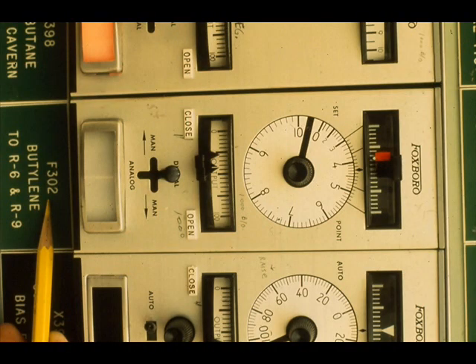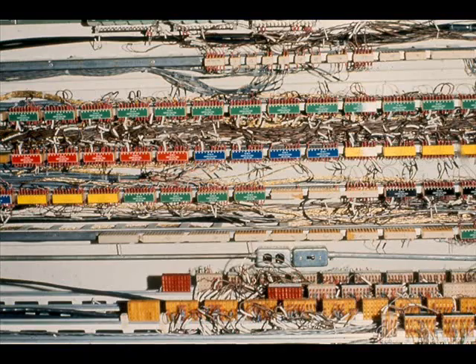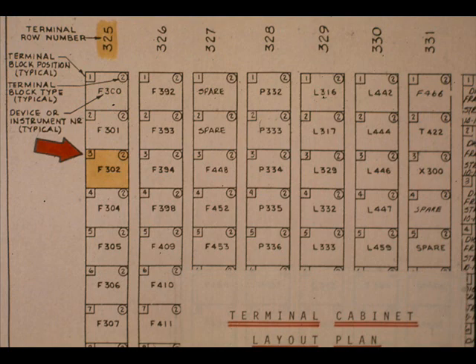Each cabinet has a terminal directory or layout drawing. This is the terminal layout for panel 4. Locate TB325-3. TB325-3 is in terminal row number 325. It is the third block from the top.